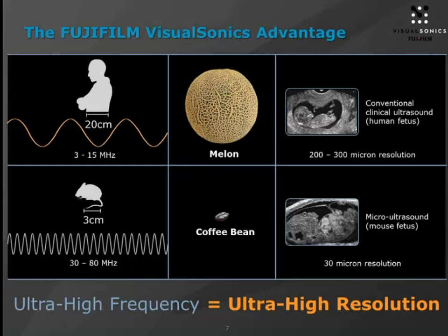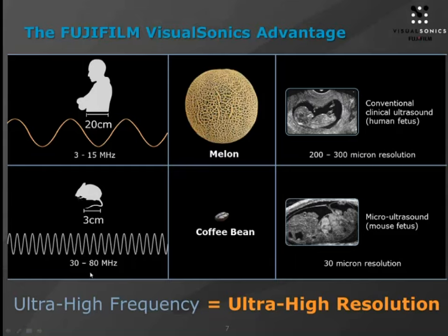Just to get everybody up to speed, I wanted to show this slide which describes the major differences between the Fujifilm Visual Sonics implementation of ultra-high frequency ultrasound versus the clinical implementation. Clinical ultrasound is typically in the range of 3 to 15 megahertz with lots of depth of penetration able to non-invasively image major areas of the human body. Our implementation starts at 15 megahertz and goes all the way up to the 80 megahertz range, giving us extremely high resolution at the sacrifice of depth of penetration — a great application for small animal imaging. You can see comparative grayscale images of a mouse fetus versus a human fetus.